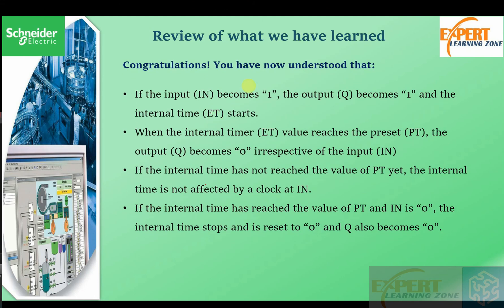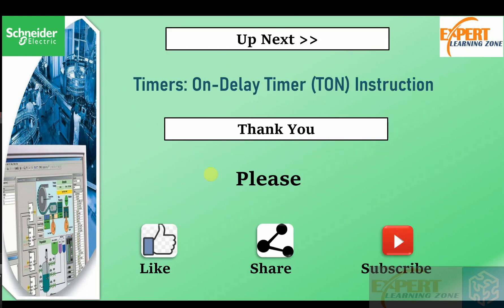Let's review what we have learned. For a pulse timer: if the input becomes one, the output becomes one and the internal timer starts. When the internal timer value reaches the preset value, the output becomes zero, irrespective of the state of the input. If the internal timer has not reached the preset value, the internal timer is not affected by the clock on the input. If the timer has reached the preset value and the input is zero, the timer stops and resets to zero, and Q becomes zero as well.